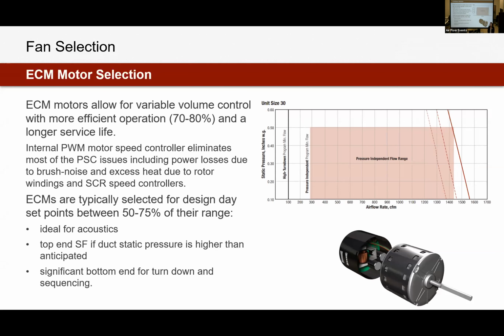I'm not understanding the question. If we have a lower turn down now at 20% instead of 33%. Yeah, well, the heating CFM is gonna change. Usually it's like half, right? Sometimes it's even lower. And then what was the other part? Maximum heating airflow will be 50%. Maximum heating CFM is gonna be 50%. So if you're an 800 CFM box in cooling, the max heating is gonna be 400. You almost need like two different diffusers. Yes. So we can talk about that.